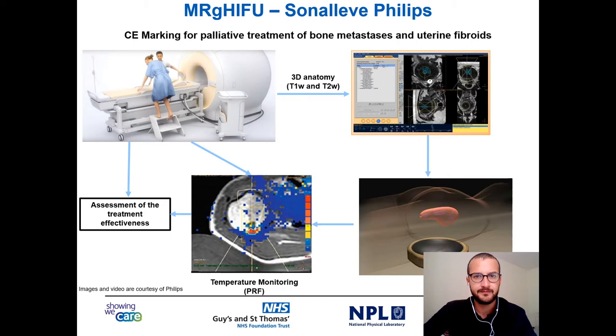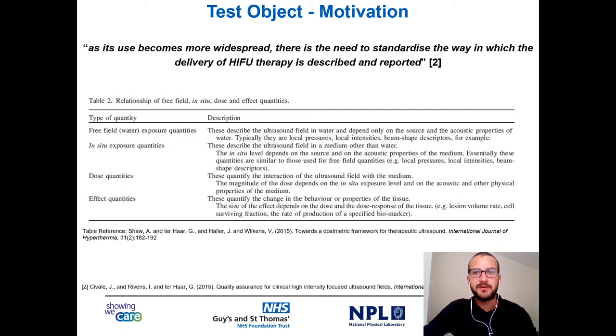So why do we need the test object? The use of HIFU is becoming widespread, and there is the need to standardize the way in which the therapies are described and reported. The main ultrasound field parameters, such as local pressure or local intensities, are well described in water. However, there is the need to define parameters for describing the interaction of the ultrasound fields in the medium. In other words, we need dose quantities, something equivalent to the absorbed dose or the equivalent dose that is used in ionizing radiation.